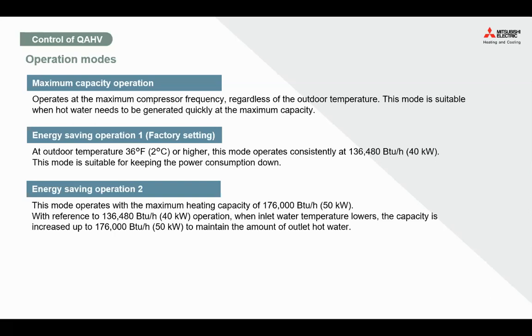leaving water temperature. So basically 3 modes. One is let the unit run based on its highest possible capacity, just ramp it up and down automatically based on what's required. Or you can lock the temperature or lock the capacity at 2 degrees C and above, just to make sure it is not drawing unnecessary power if not required. And then thirdly is somewhere between energy saving operation 1 and the maximum capacity, where it will be able to lock the unit up to 176 MBH of heating capacity, depending on your inlet water temperature and your set temperature, as well as requirement and the GPM. So 3 very flexible operation ranges for you to choose depending on what's required to achieve that extra level of energy efficiency.